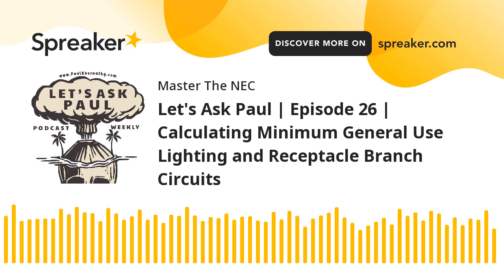With that said, there are some required branch circuits that you need to be aware of in a dwelling. You have to have a minimum of two 20 amp small appliance branch circuits, 210.11(C)(1). Okay, and of course, 210.52(B)(1) reiterates that as well when it gives you those countertop requirements. You have to have at least one 20 amp laundry branch circuit, required in 210.11(C)(2).